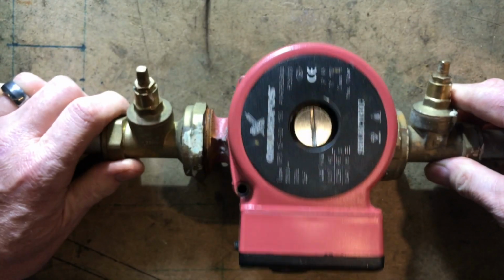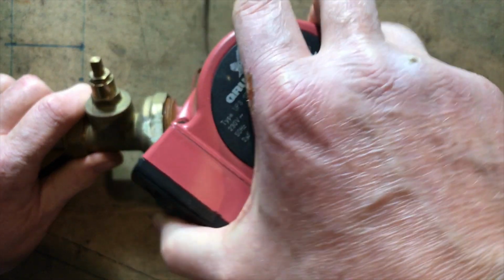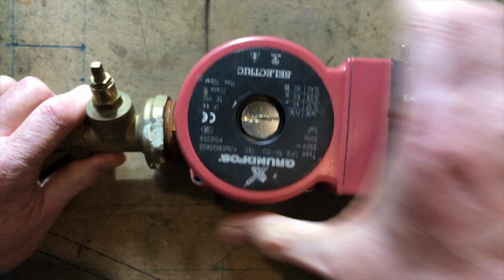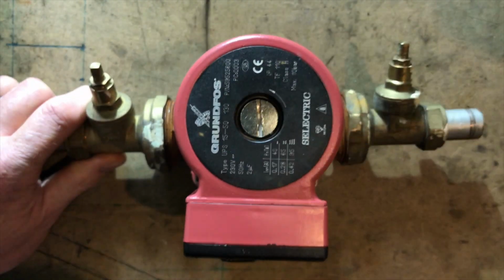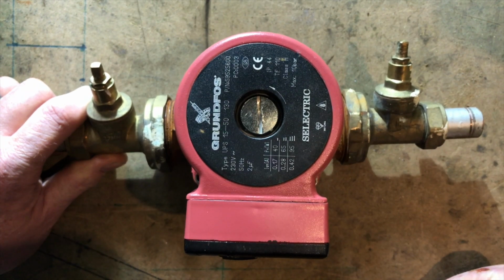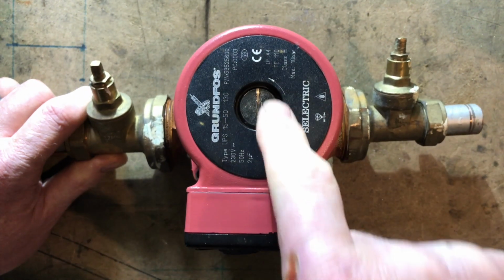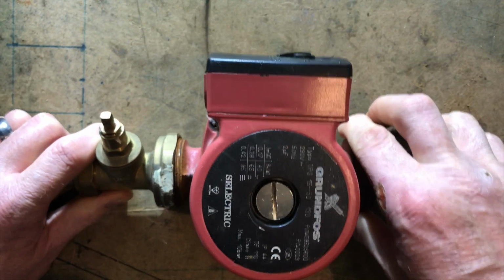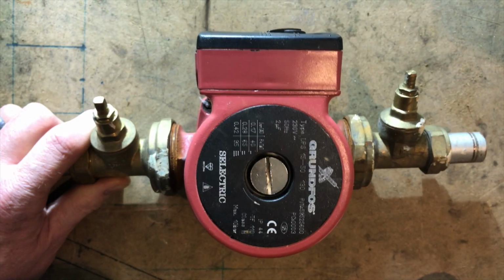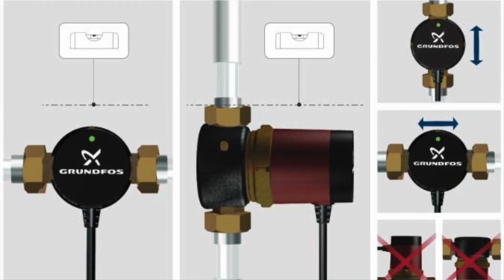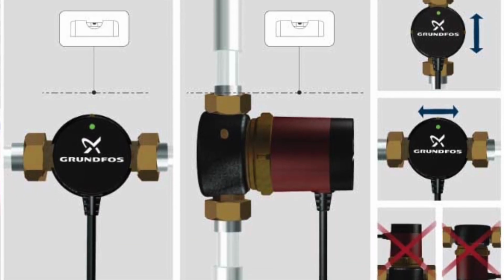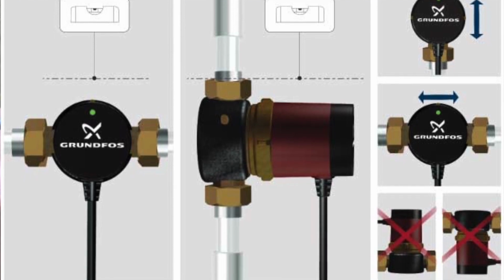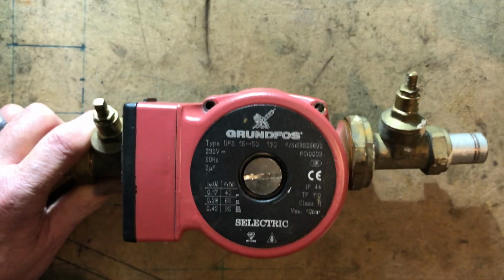Now the other thing is, depending on which way the pump is installed, you can actually have 4 different directions of where you can spin the head and it will still work. Because one thing you don't want to do is you don't want the electrical connection to be down at the bottom, because obviously when you're bleeding it here, the water would run down into the power. And you also want the electrical connection at the top, so you could always get at the electrical connections when it's in situ. So always follow the manufacturer's instructions on the right rotations for installing a pump. But with these Grundfos pumps, you could spin them in 4 ways.